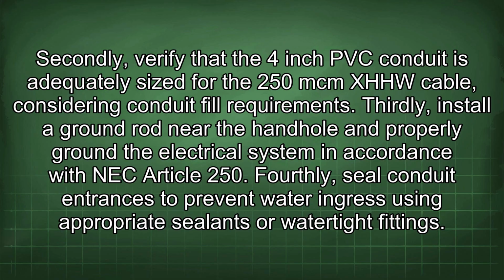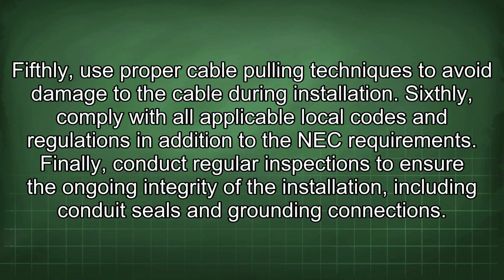Thirdly, install a ground rod near the handhole and properly ground the electrical system in accordance with NEC Article 250. Fourthly, seal conduit entrances to prevent water ingress using appropriate sealants or watertight fittings. Fifthly, use proper cable pulling techniques to avoid damage to the cable during installation. Sixthly, comply with all applicable local codes and regulations in addition to the NEC requirements. Finally, conduct regular inspections to ensure the ongoing integrity of the installation, including conduit seals and grounding connections.